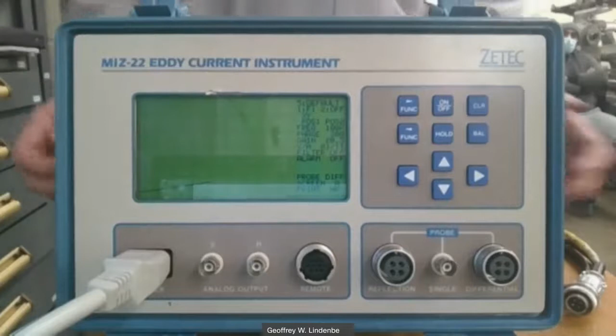Below that is our gain. The gain is the sensitivity of the detector. So remember, we've got a frequency generator or a signal generator that's going to send AC. In this case, right now it's set to 100,000 hertz AC to the probe, or to the coil in the probe. And that AC is going to create a magnetic field.